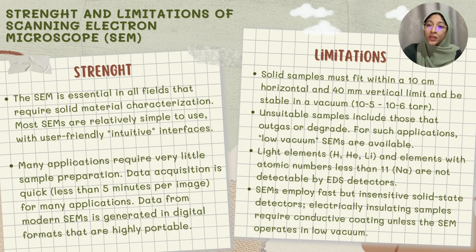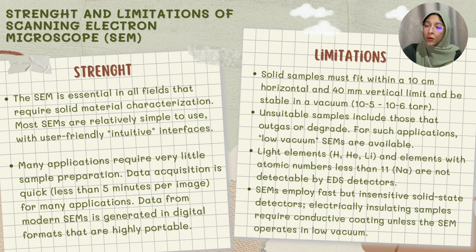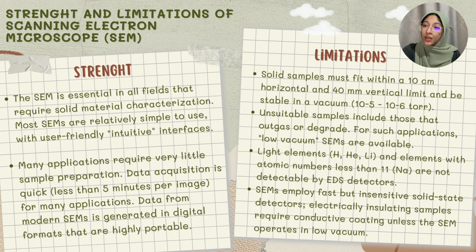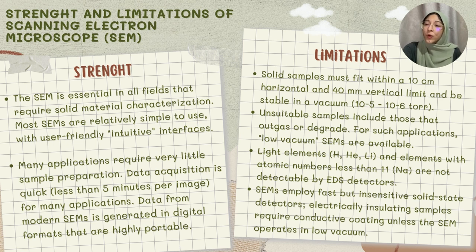Data from modern SEMs is generated in digital formats that are highly portable. However, for the limitations of SEM: a solid sample must fit within a 10-centimeter horizontal and 40-millimeter vertical limit and be stable in vacuum. Unsuitable samples include those that outgas or degrade, though low-vacuum SEMs are available for such applications. Light elements with atomic numbers less than 11 are not detectable by EDS detectors, and electrically insulating samples require conductive coating unless the SEM operates in low vacuum.